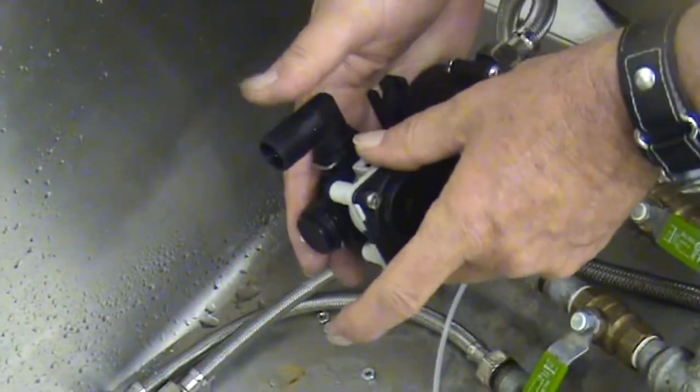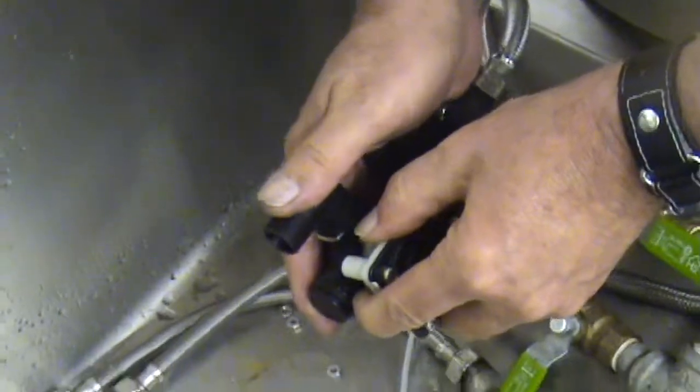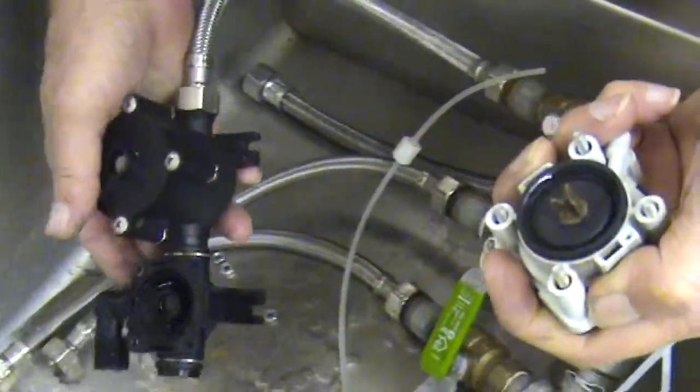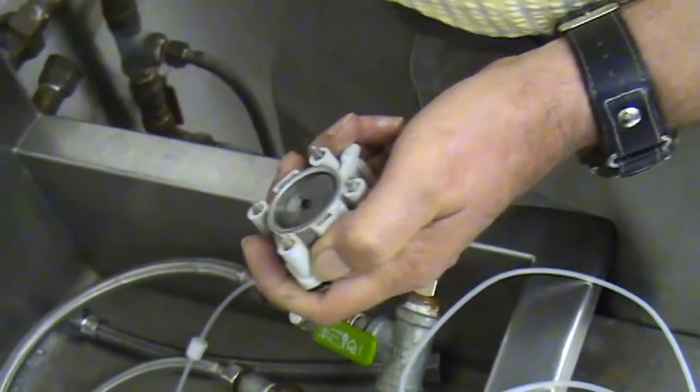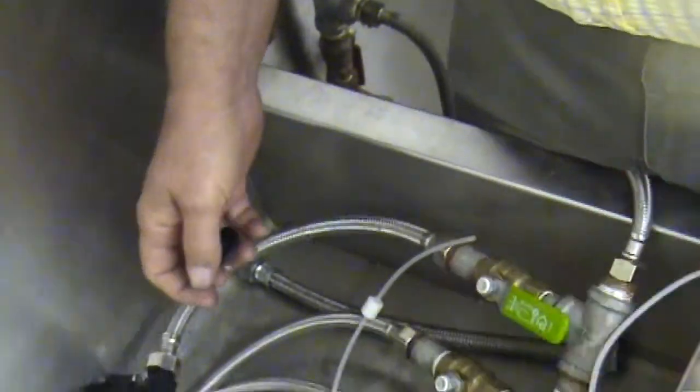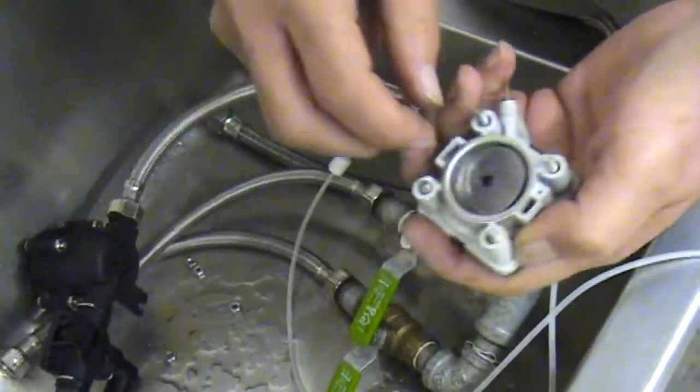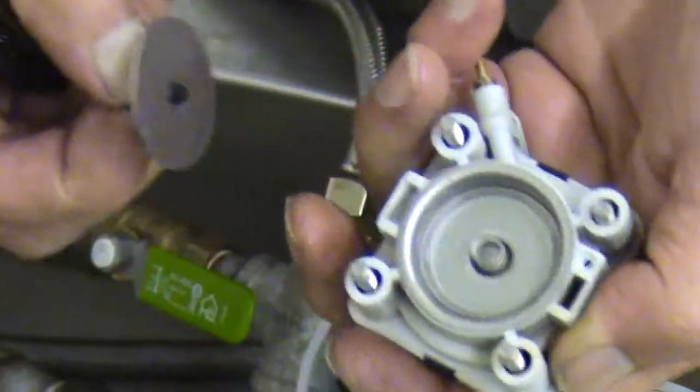When you take the servo motor off, grab it by the white part, pull straight up, it will come off. As you can see we've got the water diaphragm came off with the servo motor. You'll notice the orifice plate and the little spring are held in place by the magnet in the servo motor.